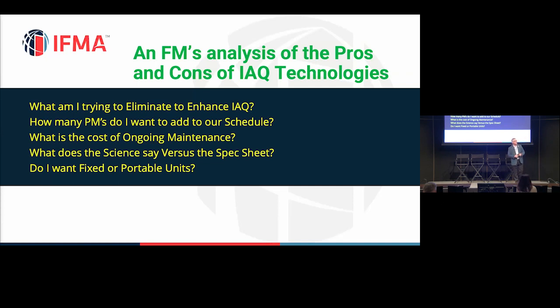I had a statement. I have a lot of buildings that have the 6 air changes per hour, and when COVID hit, everyone's like MERV 13, all that. It would kill the system because you're blocking the airflow. You can't put that amount of filtration in existing systems. So that's why I was looking at UV as a possible solution. But I was looking at UV in the supply trunks. But then you're just telling me the 20 feet, is that codified somewhere in a study where they need that amount of feet? Yes, it is. Okay. It is, yep. And somewhere I've got that reference, I can get it. I thought that was my magic bullet for a minute, but.